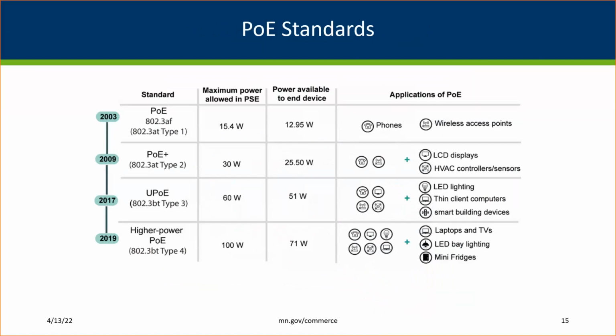The first PoE standard was ratified in 2003 with 15.4 watts of power allowed from each port of the network switch. Since then, updated standards have resulted in higher powered PoE network switches becoming available. Over the last 3 to 4 years, as power levels exceeded 60 watts, the variety of end uses that could be powered by PoE increased the potential of PoE to be a backbone for connected devices and DC distribution. 100-watt PoE switches are now coming onto the market.